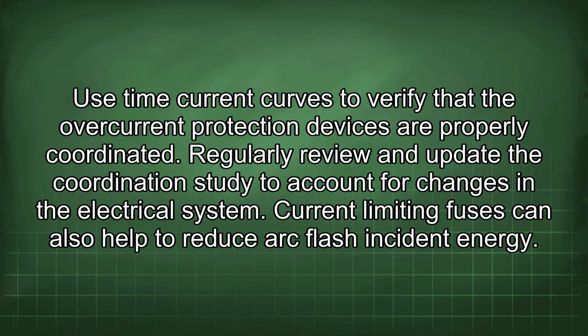Use time current curves to verify that the overcurrent protection devices are properly coordinated. Regularly review and update the coordination study to account for changes in the electrical system. Current limiting fuses can also help to reduce arc flash incident energy.